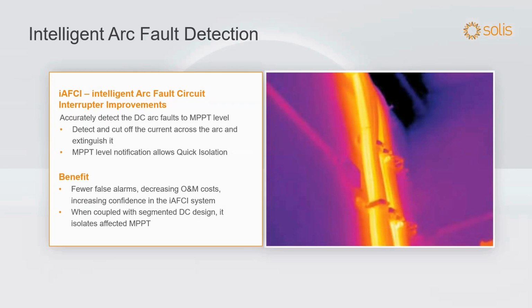But since there's two per MPPT, you can actually Y connect in the field and bring a single pair back, because each pair of terminals is capable of handling the full MPPT power. So that's interesting. But for me, I'm old school, so I like you to bring back all of the strings, because as I know, this AFCI alarm will tell you exactly what string it's on. And you just get better data that way.